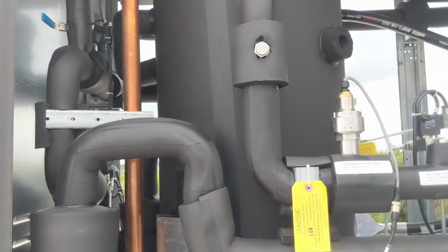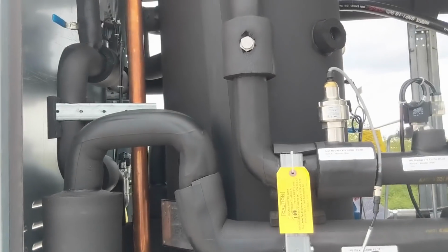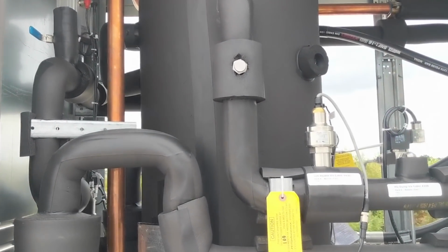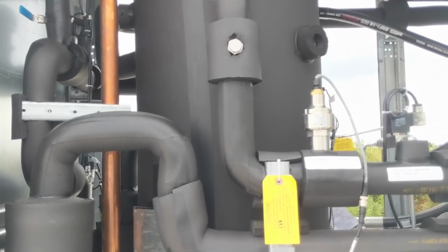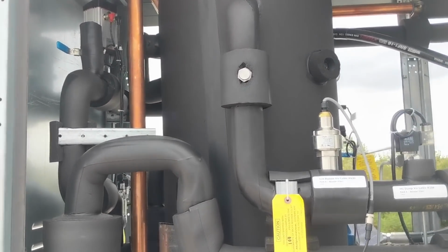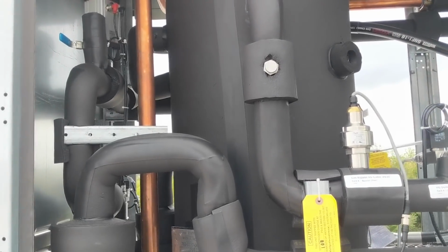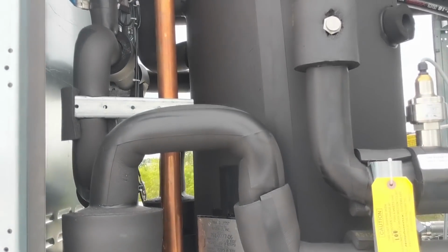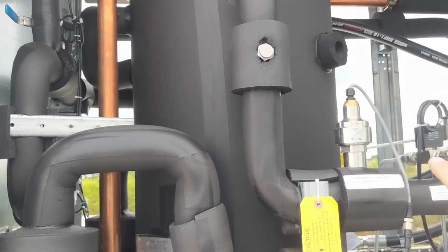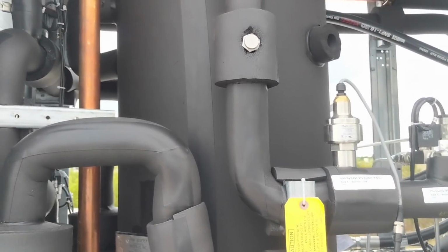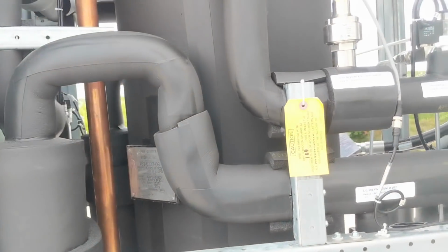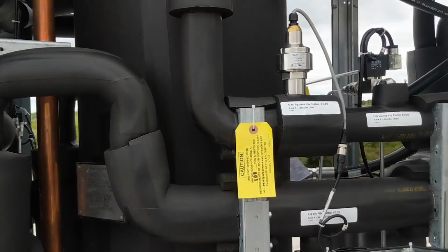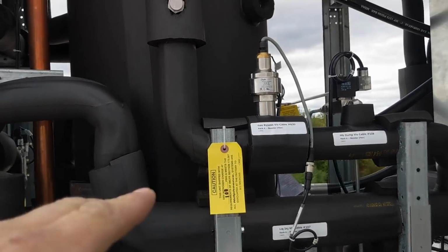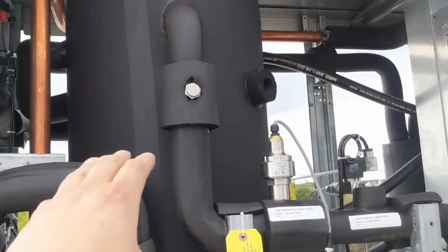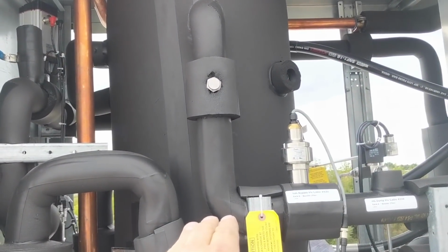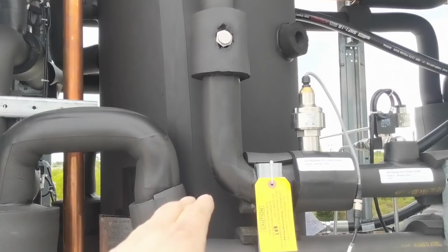Because over an 87 degree temperature, CO2 no longer is a liquid, a vapor, or a gas. It's transcritical. It's an unstable fluid. So what we have to do is falsely turn it back into a liquid. So we hold back a little bit of pressure. We open the flash gas bypass to reduce the tank pressure. We get it down to 500 pounds. It's about a 30 degree evaporator or 30 degree condensing temperature. The tank starts to drop pressure and temperature at the same time, and we end up with a liquid again.